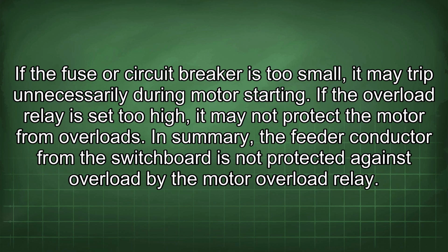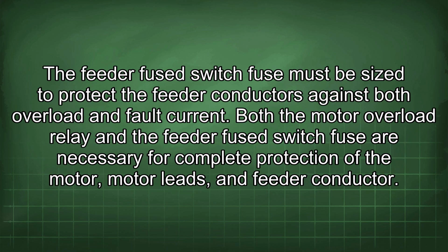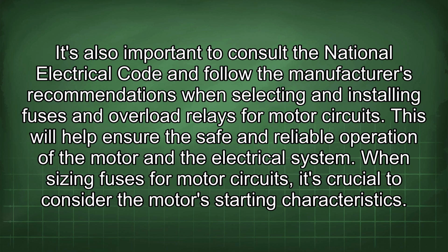In summary, the feeder conductor from the switchboard is not protected against overload by the motor overload relay. The feeder fuse switch fuse must be sized to protect the feeder conductors against both overload and fault current. Both the motor overload relay and the feeder fuse switch fuse are necessary for complete protection of the motor leads and feeder conductor. It's also important to consult the National Electrical Code and follow the manufacturer's recommendations when selecting and installing fuses and overload relays for motor circuits. This will help ensure the safe and reliable operation of the motor and the electrical system.